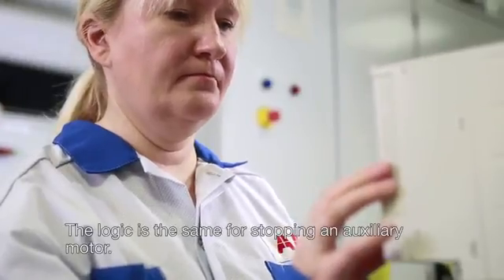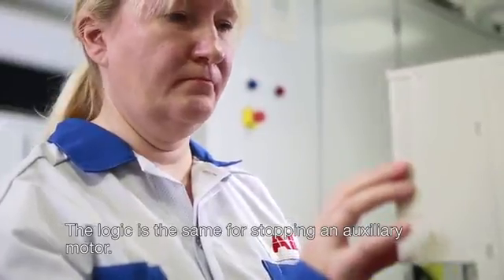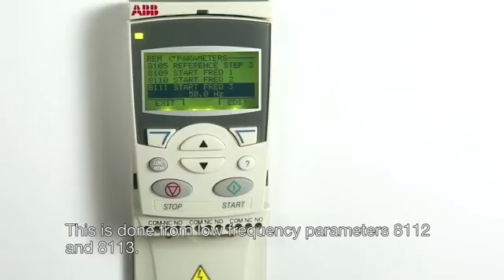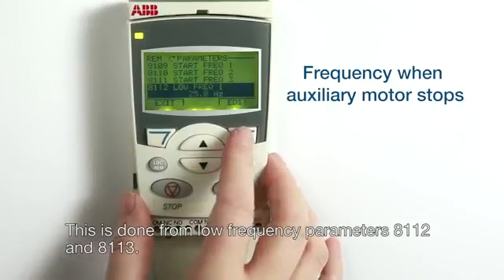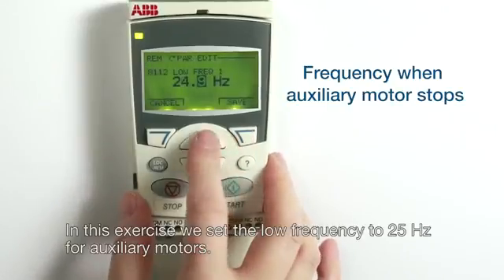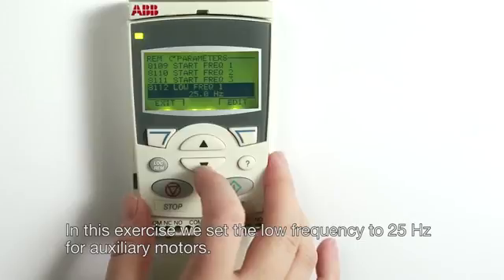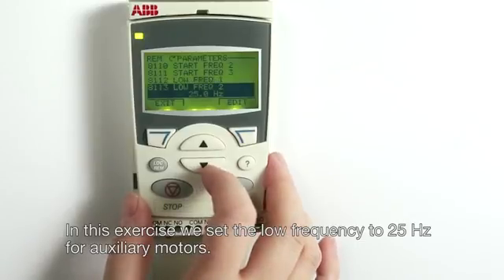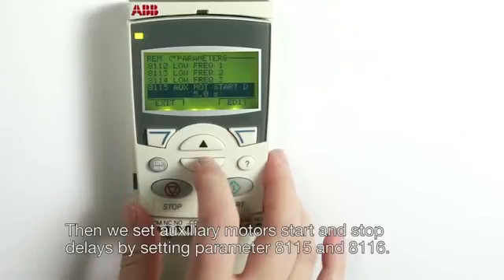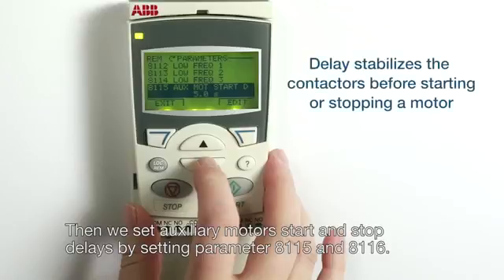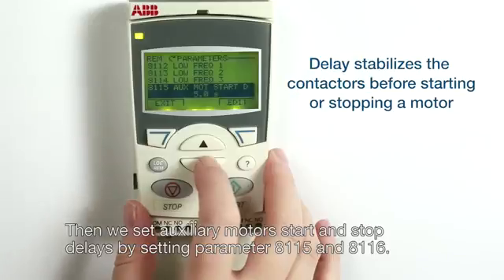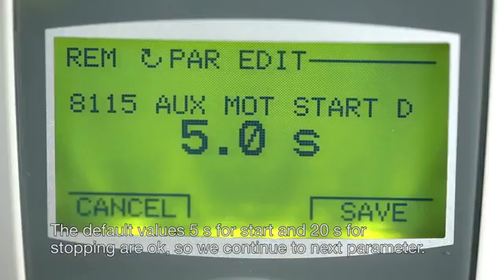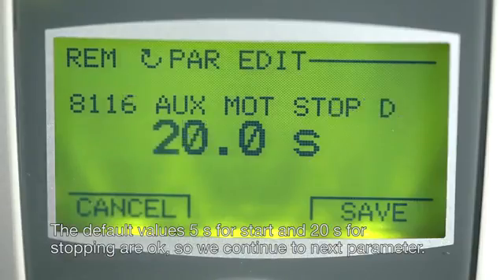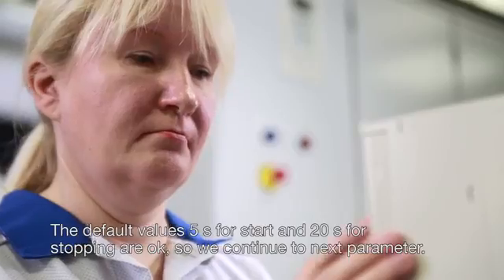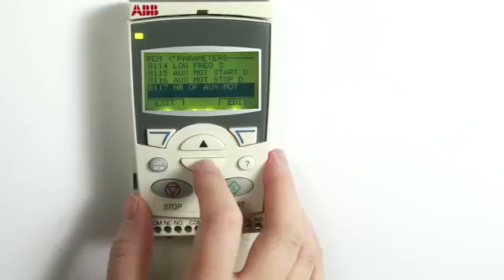The logic is the same for stopping an auxiliary motor. This is done from low frequency parameters 8112 and 8113. In this exercise we set the low frequency to 25 Hz for auxiliary motors. Then we set auxiliary motors start and stop delays by setting parameters 8115 and 8116. The default values, 5 seconds for start and 20 seconds for stopping, are OK, so we continue to the next parameter.